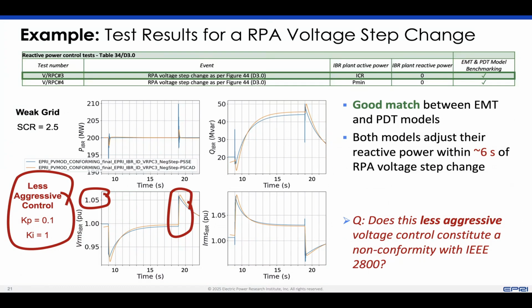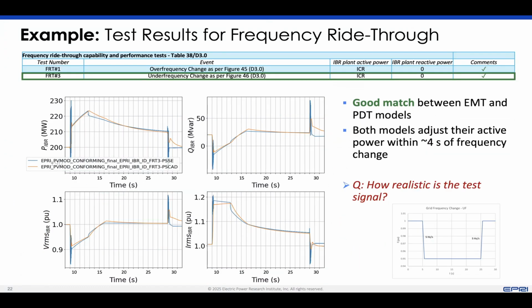Those are approaches and questions you can ask yourself. And then for the frequency ride-through, we've run a similar test. Now we're using the test signal from 2800.2, and it goes all the way to the edges of the ride-through zone. That is like a 5 hertz per second rate of change of frequency, all the way down to 0.95 per unit of 60 hertz.